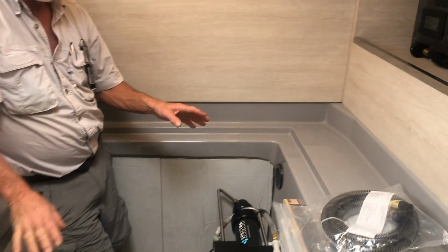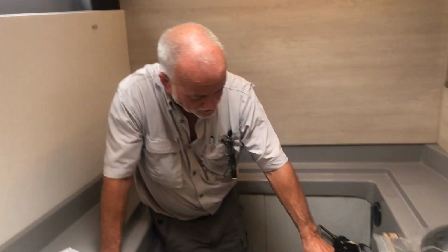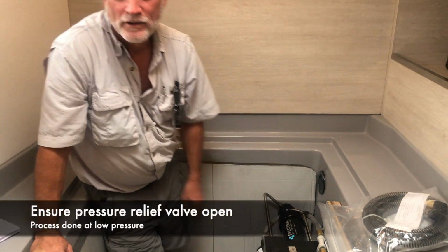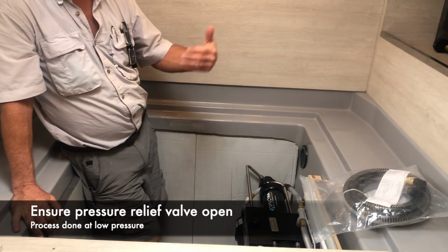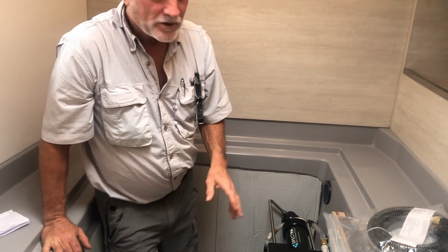Okay. And we're just going to let it circulate like that for about 20 minutes. When that's done, shut it all off, reconnect all the hoses back to where they belong, and you're done. Okay. But it will be with the pressure relief valve open. Because you don't want to pickle or unpickle it with it under pressure. When you get to the point you're going to pickle it, that's when my phone will ring. Okay? And I'll remind you.